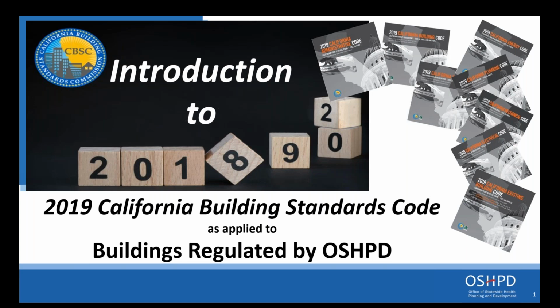Perfect. Yeah, I'd actually like to expand on that. An example of this, if you're adding subacute to a skilled nursing facility, Bill mentioned that you'd be required to add that third branch. That would be only for that area of the building that's being served by that service. So the same thing would apply here. You would only have to provide the additional service for the area that's actually providing that service.